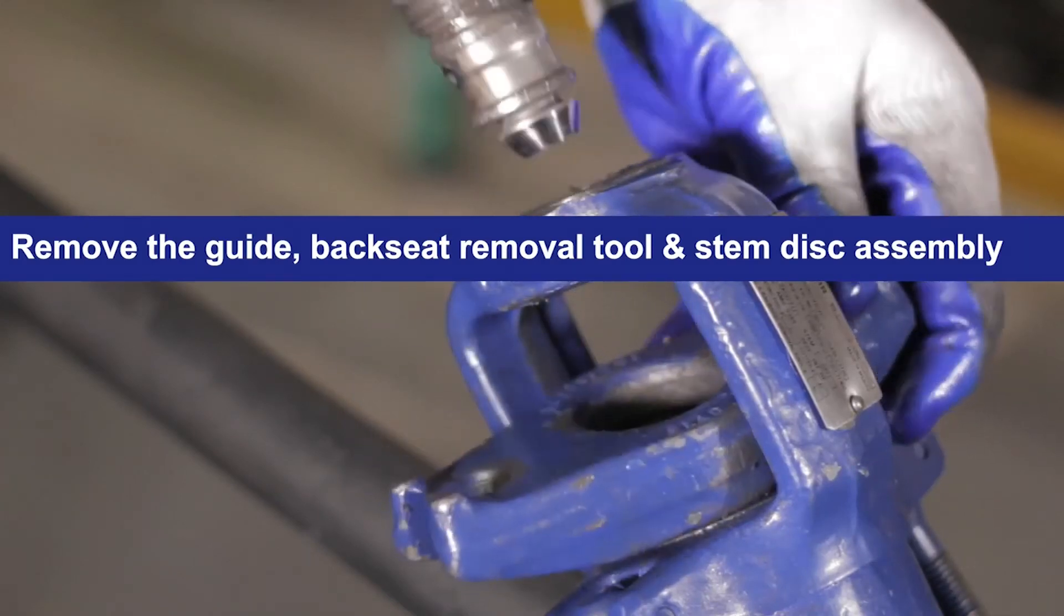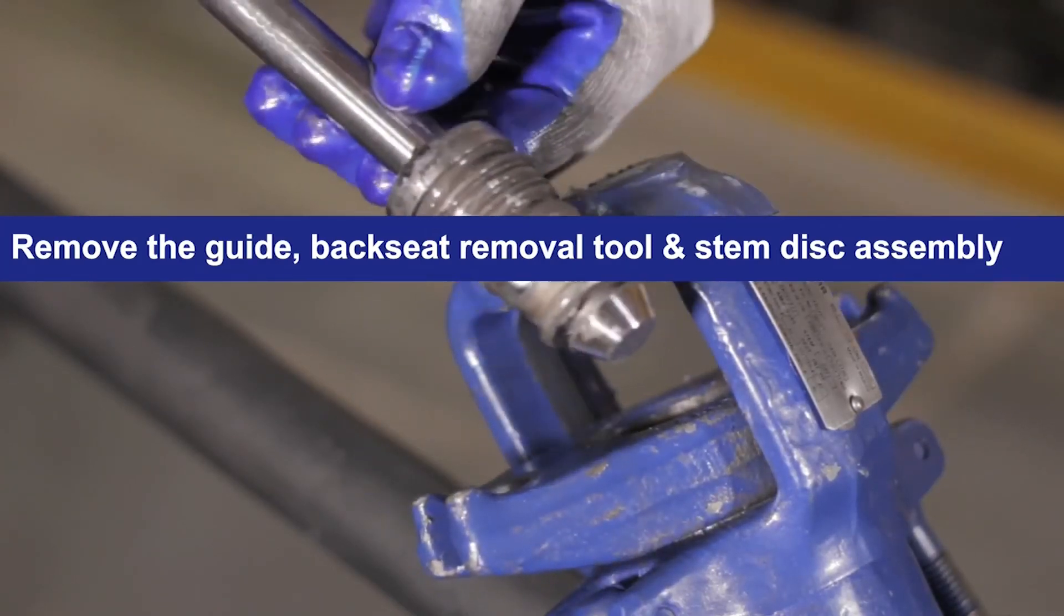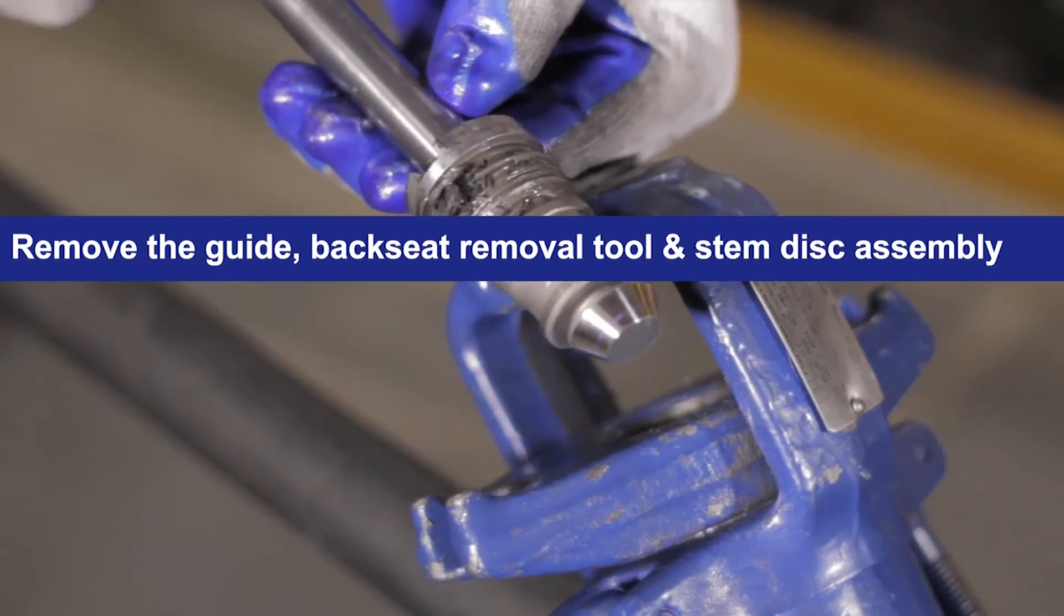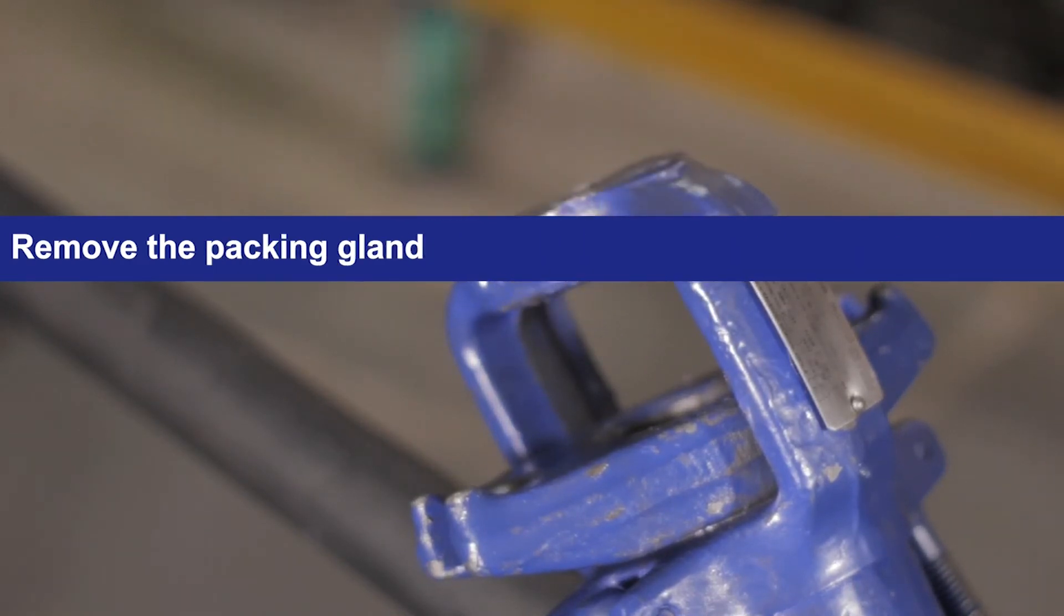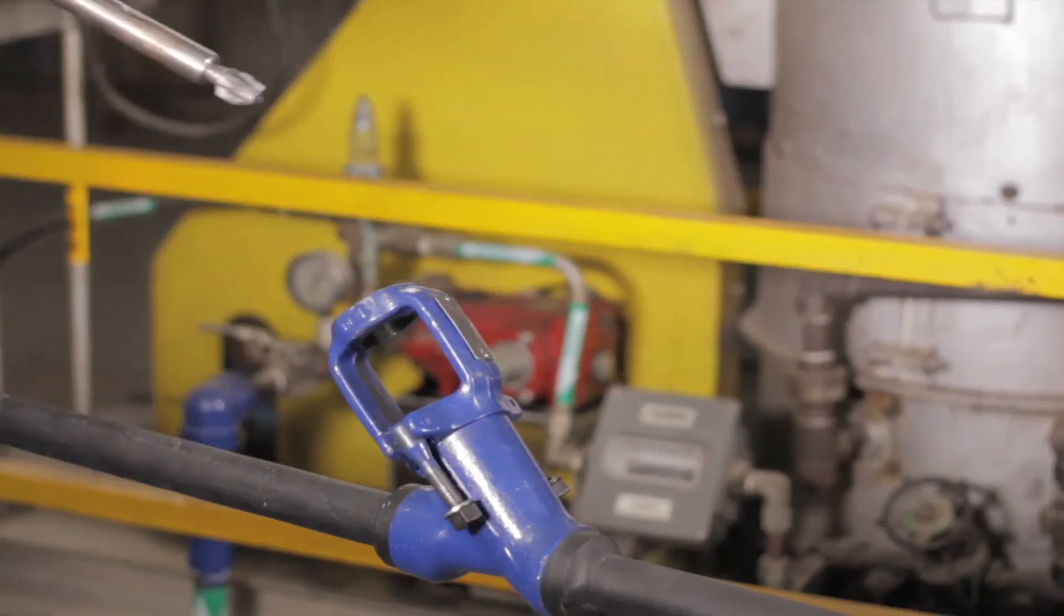You can now remove the guide, the backseat removal tool, and the stem disc assembly out of the valve's body. You should also remove the packing gland. The valve seat is now ready to be reconditioned.